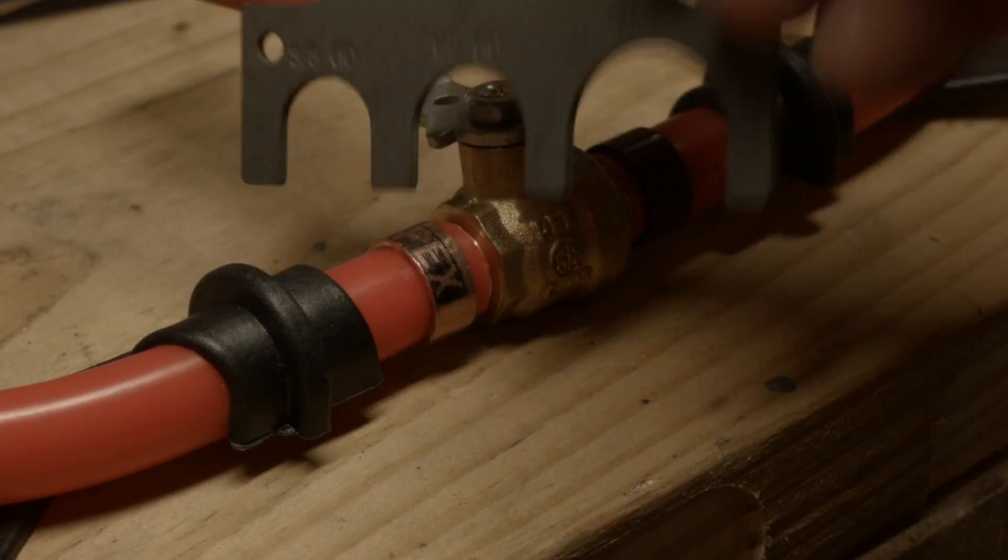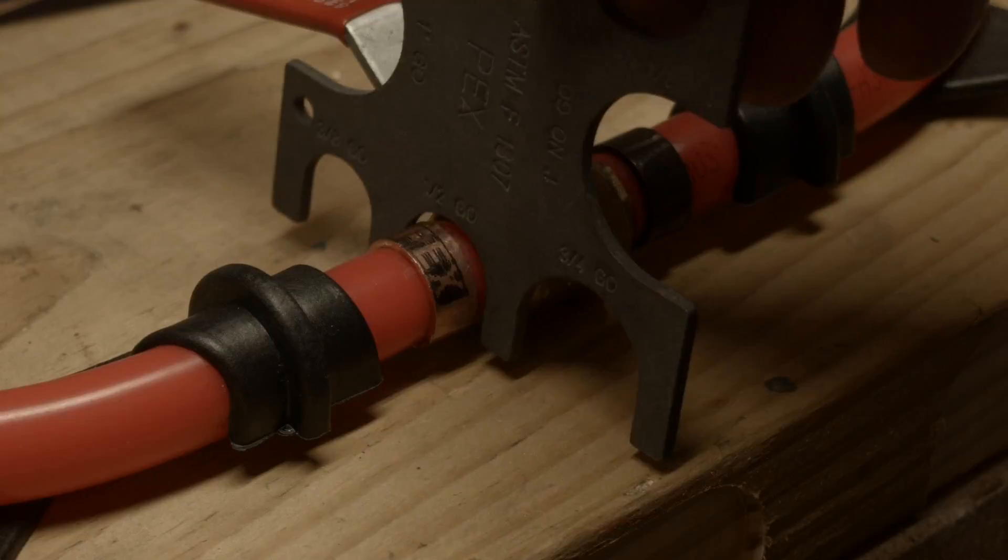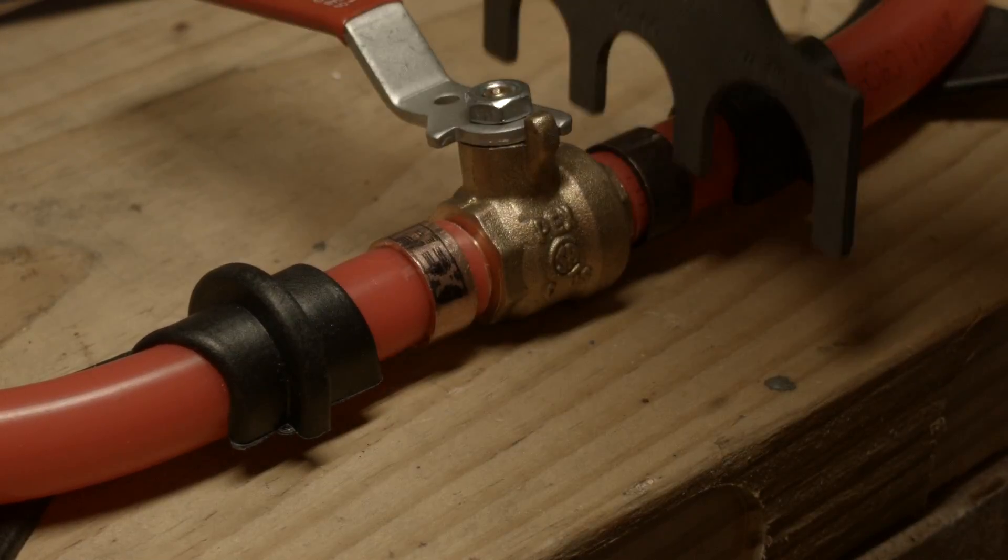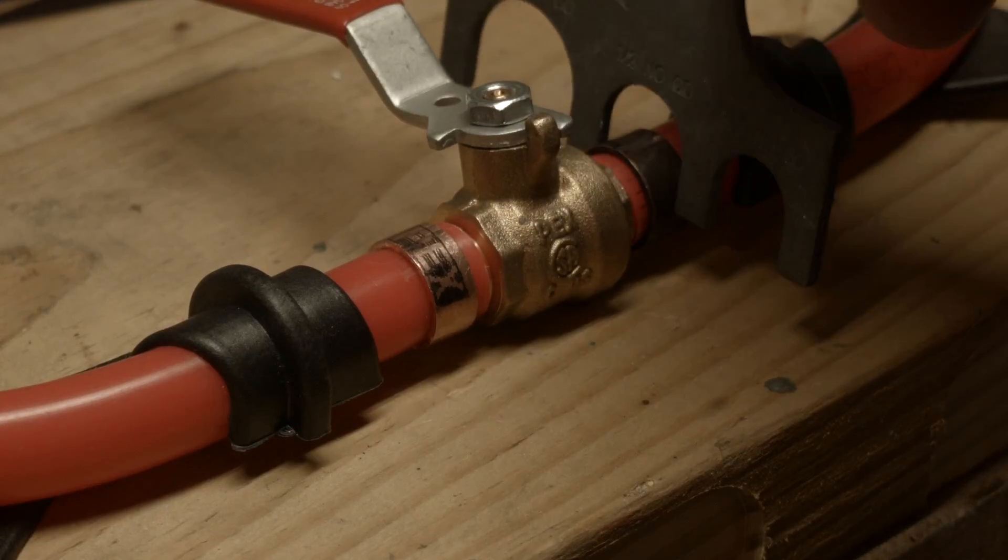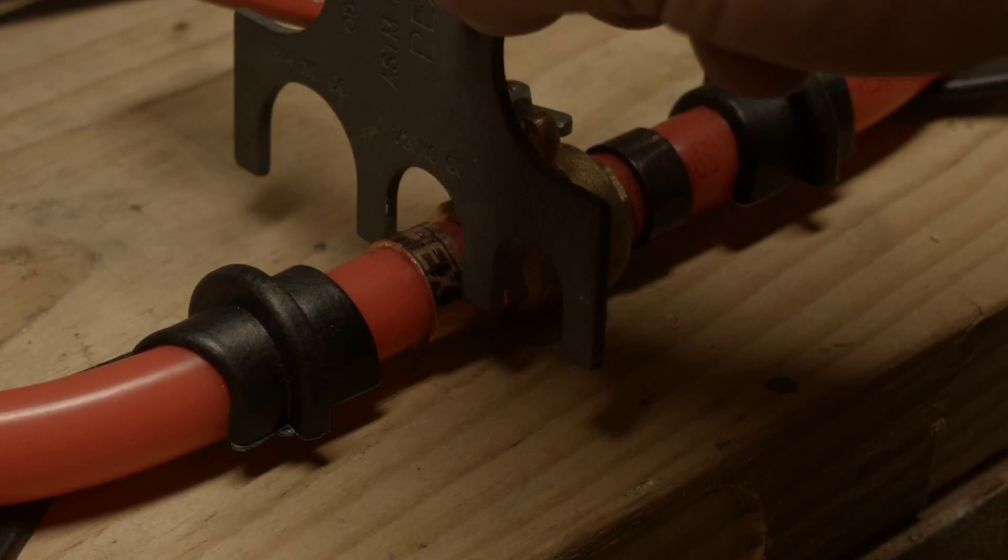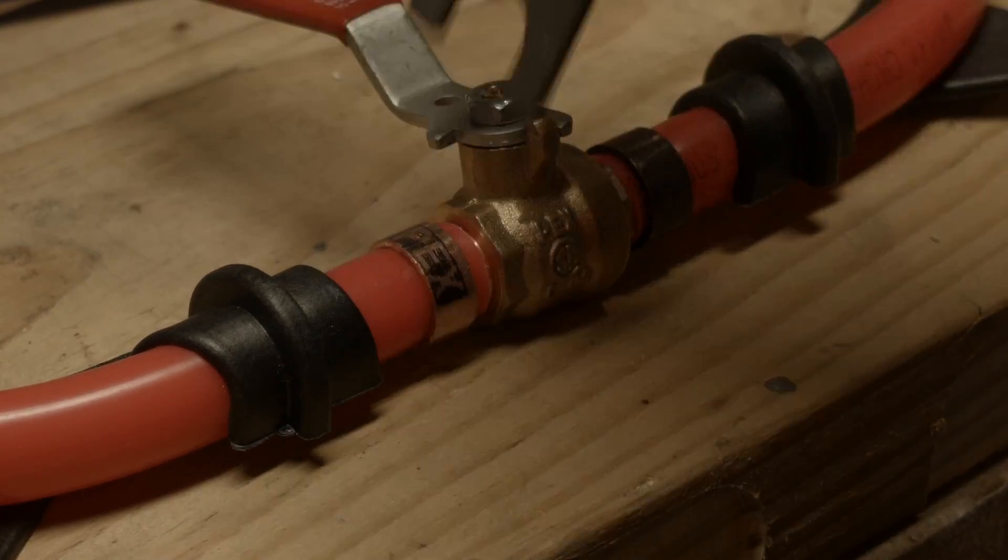Now the half-inch go has to fit over it. Easy, like this. And the no-go has to get stuck. So the no-go does not fit. If the no-go fits, then something went wrong.